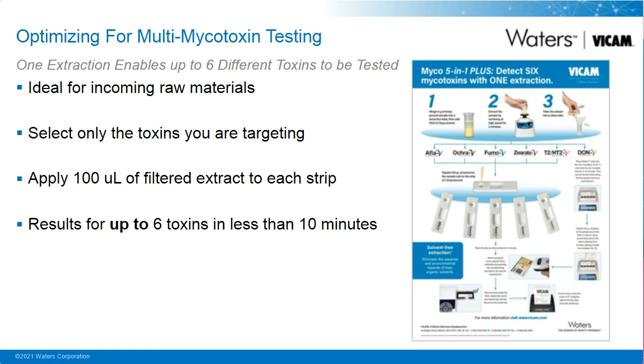Method validation for the strip test is carried out comparing the results with standard methods such as LC or LC mass spectrometry. We gear our validations to ensure that we meet the sensitivity and the range that's required not just by the industry but by governing bodies such as the USDA. And here you see we have 3 of the strip tests already approved by the USDA Federal Grain Inspection Service, and we expect more to come in the future.